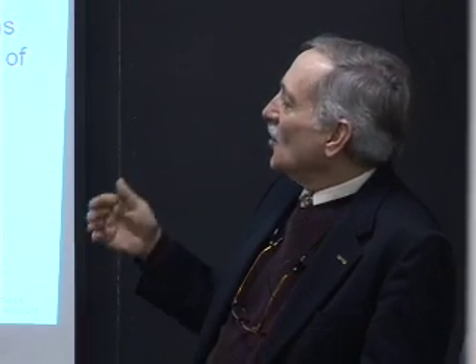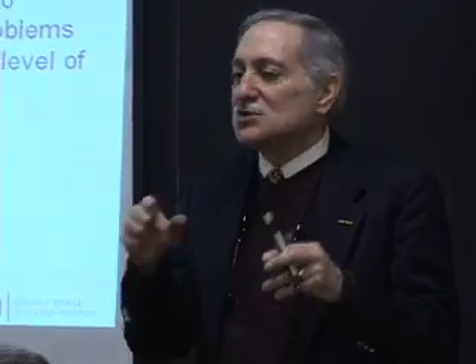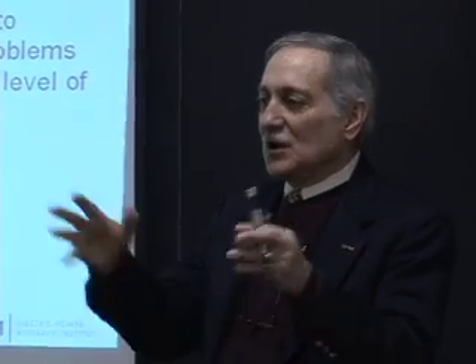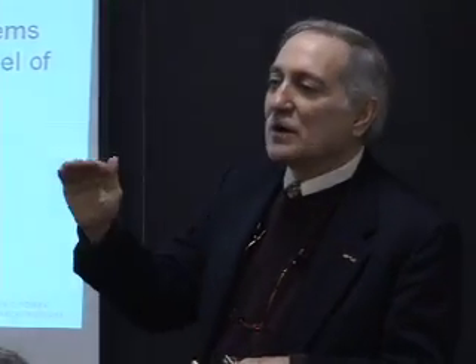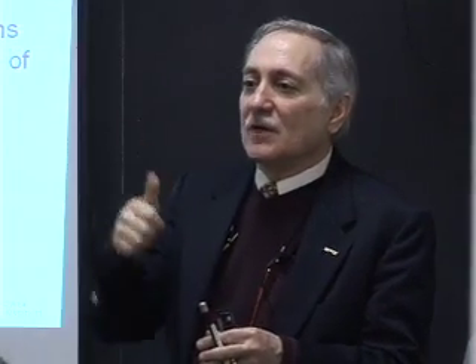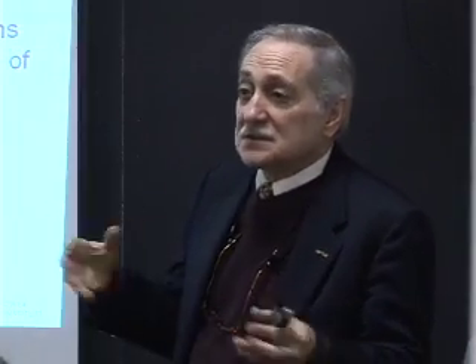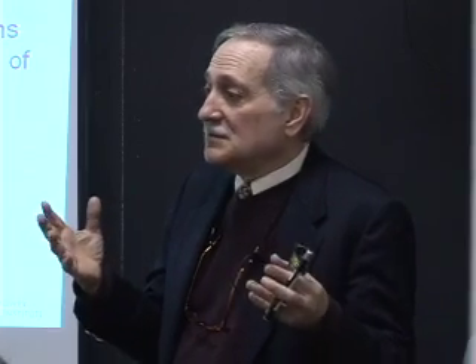There are a couple of ways to build short circuit current limiters. One of them uses a superconductor, because a superconductor has a very nice property: it's almost zero resistance when the temperature, magnetic field, and current are below certain thresholds. Anytime one of those three gets above a threshold, the resistance jumps to very high numbers. So that's a very practical way to limit current using superconductors.